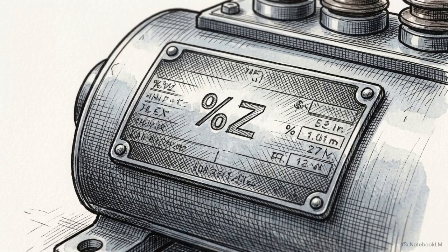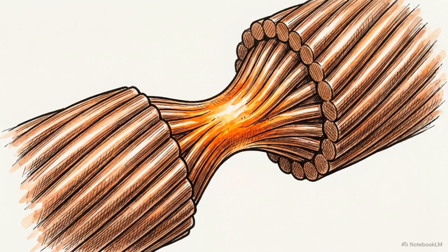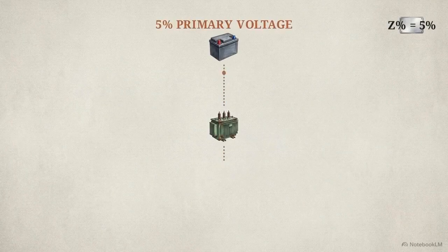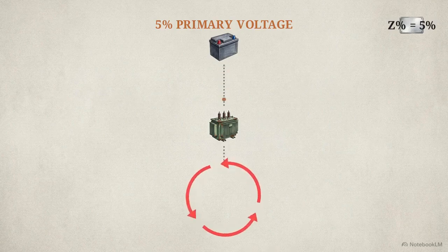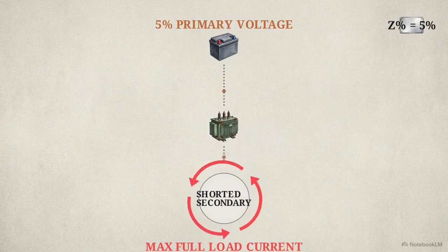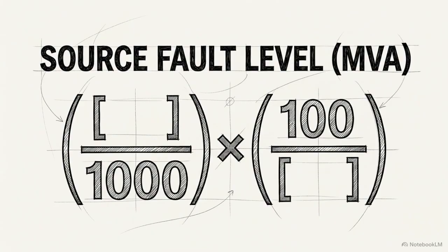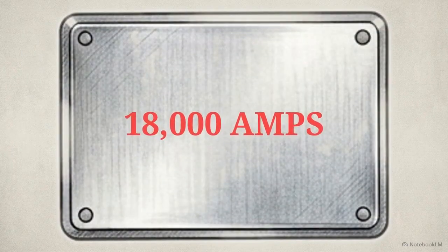With the kVA established, the next critical variable is the transformer's impedance, commonly noted as %Z. Impedance represents internal resistance. A 5% impedance rating means it only takes 5% of the normal primary voltage to circulate the maximum full load current through a shorted secondary winding. We calculate the source fault level in MVA by taking the kVA rating, dividing it by 1000, and multiplying by 100 over the %Z. For a 500 kVA unit with 4% impedance, the math yields 12.5 megavolt amperes. To find prospective fault current, divide 12.5 MVA by the square root of 3 times 400 volts. This resolves to 18,000 amps of fault current at the transformer.